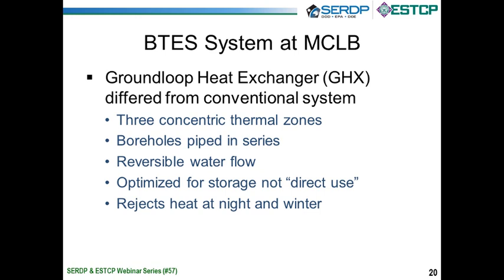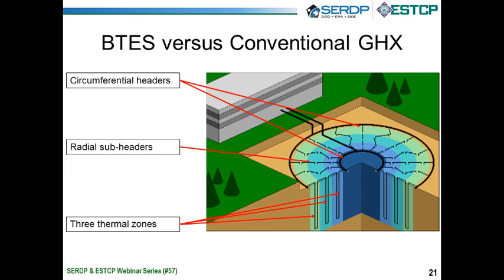And so with all this extra heat, a traditional HVAC system is working very hard to reject that at peak times. Even if you're a hybrid geothermal system, meaning you might have a cooling tower, that cooling tower is running hard and evaporating a lot of water at peak conditions. BTES is the opposite. We're dumping the heat at night and in the wintertime. We're not running these dry coolers or adiabatic dry coolers at peak periods. So we're rejecting our heat at a different time period. So those are the fundamental differences between the traditional system and a BTES system.